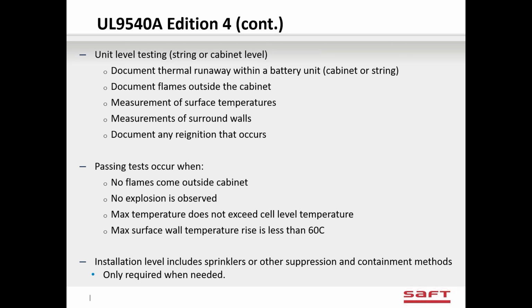It's up to the AHJ to take that report and decide whether or not he will allow you to go to a closer spacing. UL will make a recommendation that says, we don't believe spacing is necessary with this battery, if that's what they believe. But it's up to the AHJ. NFPA left the code enforcement people in control of whether or not you can go to a closer spacing.